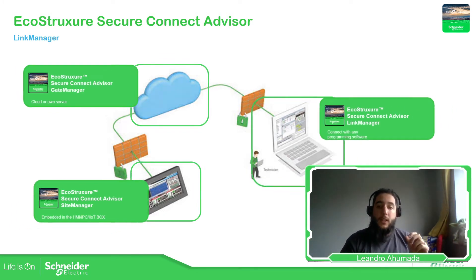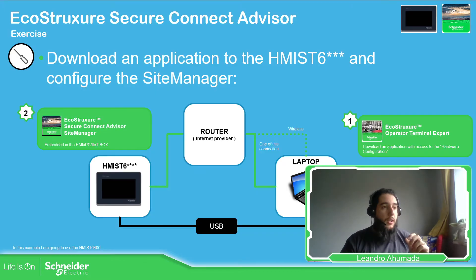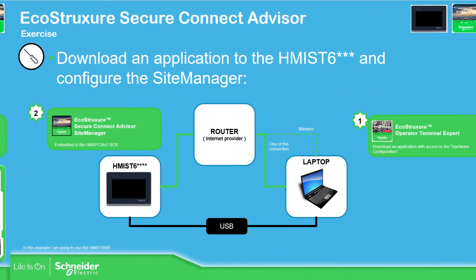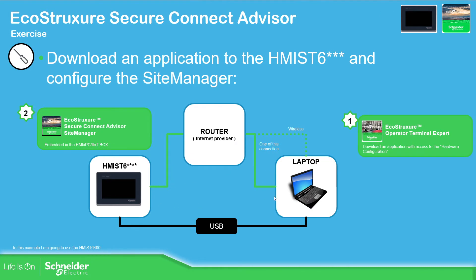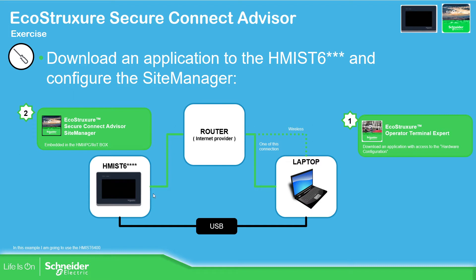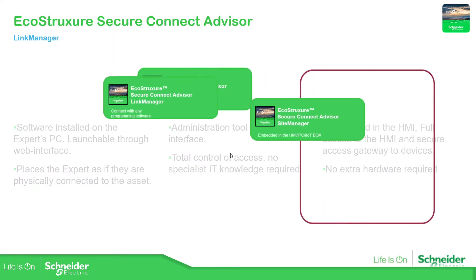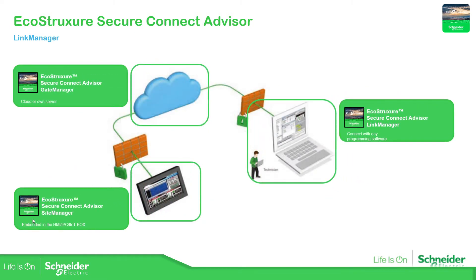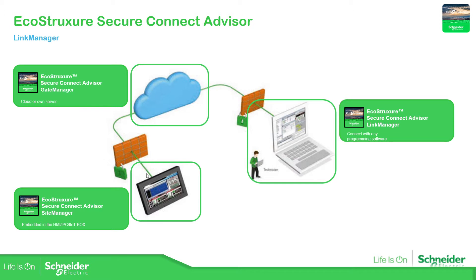So the idea that we have is to make this exercise. We're going to connect from the laptop to the HMI via USB to download the application that we're going to develop on the software EcoStruxure Operator Terminal Expert. We're going to have internet connection via router to the laptop and the HMI ST6, and on the HMI ST6 we're going to configure the Site Manager. The Site Manager is the one that we need to configure on the HMI site, and in order to connect the Site Manager to the Gate Manager there is some information that we need to share to establish this secure connection.